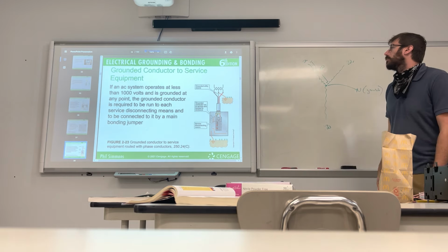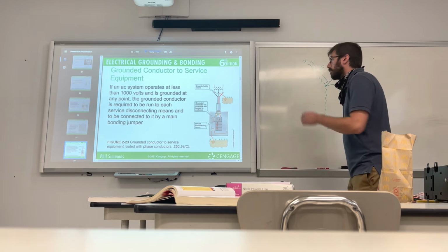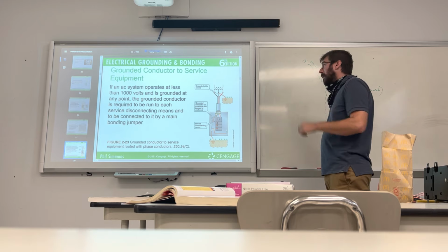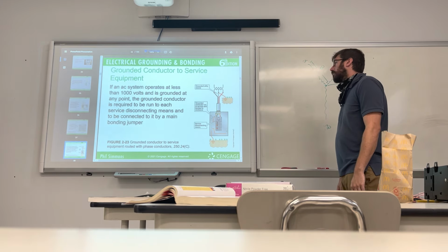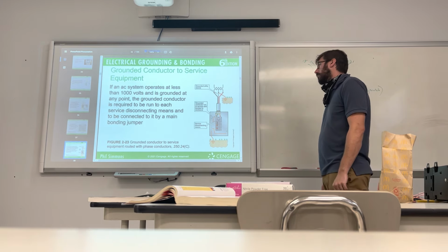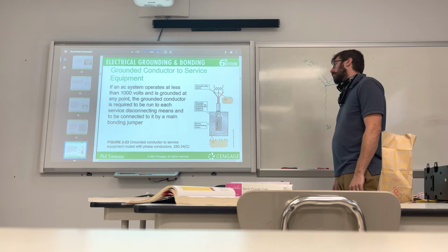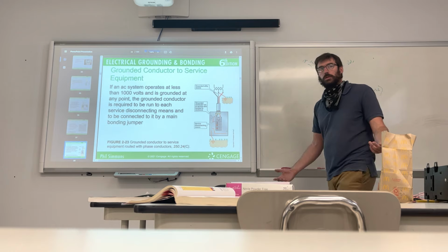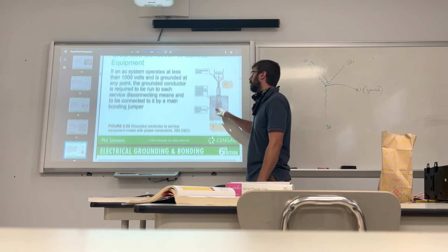Grounded conductor to service equipment. If an AC system operates at less than 1,000 volts and is grounded at any point, the grounded conductor is required to be run to each service disconnecting means and to be connected to it by a main bonding jumper. Any questions there? Nothing shocking?